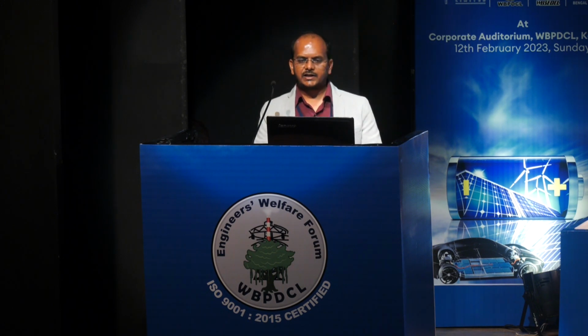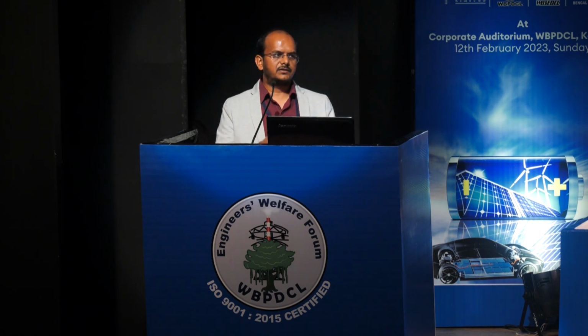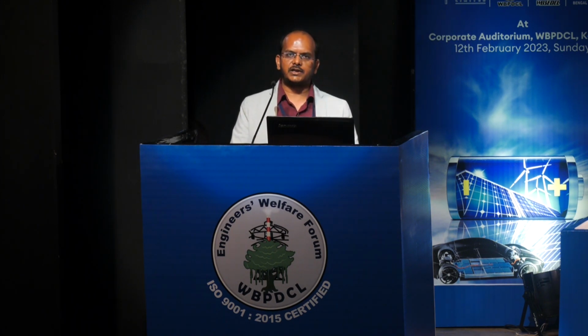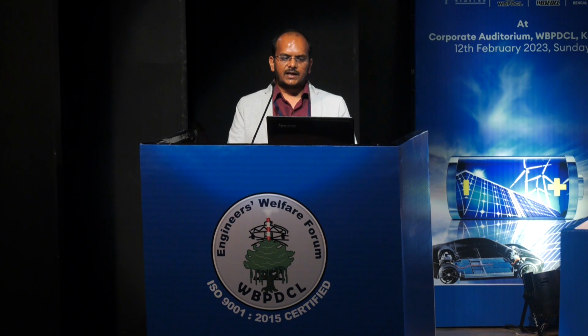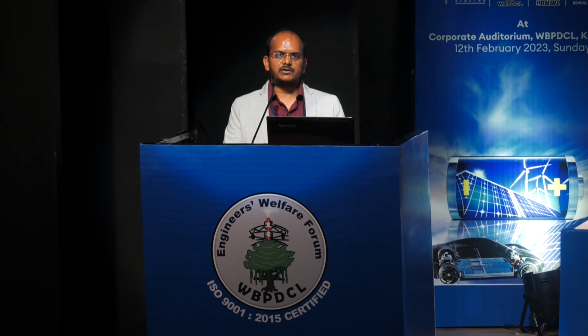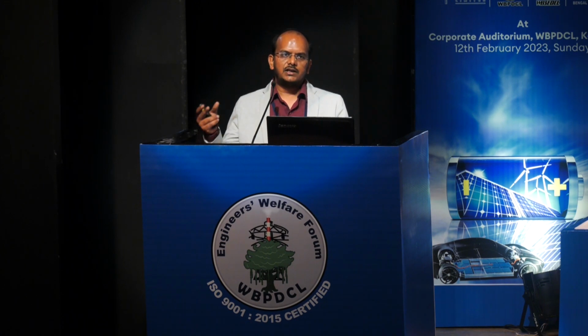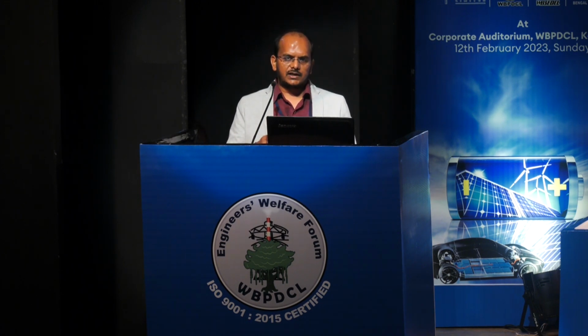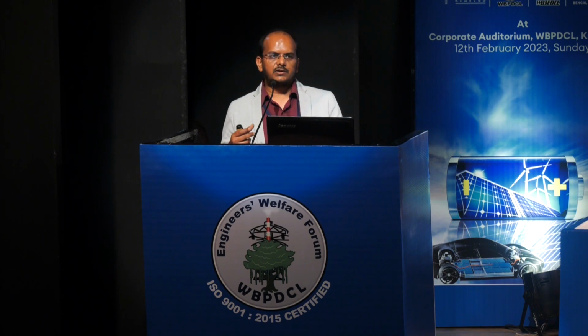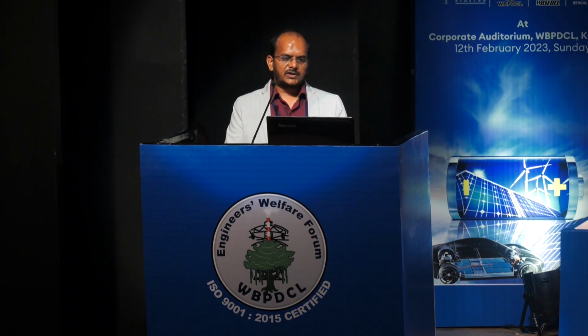The challenge with pumped hydro is that it's capital intensive. You have to invest a huge amount of money, so taking a decision of such magnitude becomes difficult, and they have long execution time. If I decide I have a requirement of pumped storage of a certain gigawatt and I start building a plant, I'll be able to get it only after 5 to 6 years. So that becomes very challenging to maintain the grid with such kind of time, and there are environmental issues with that.